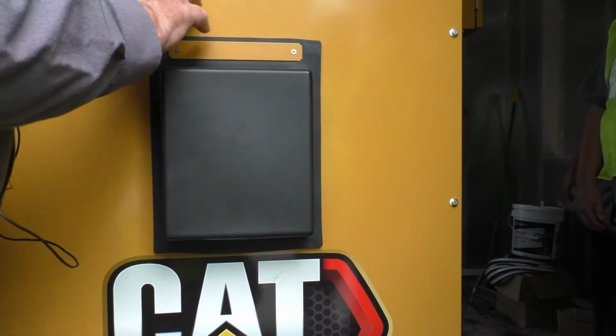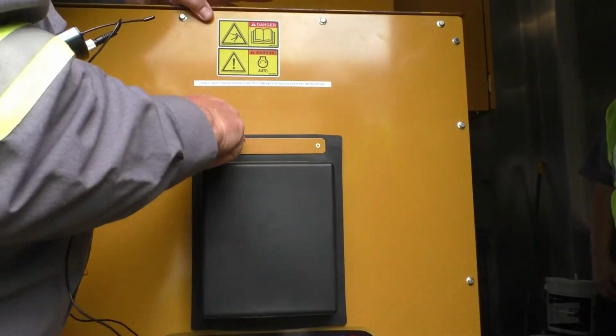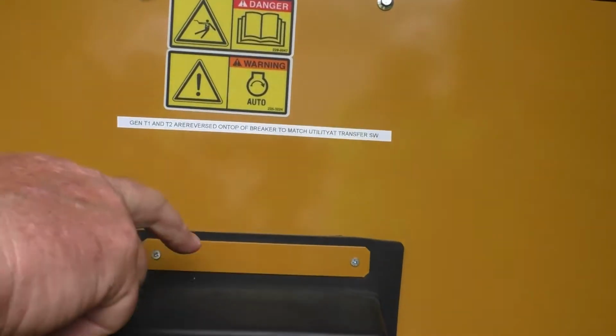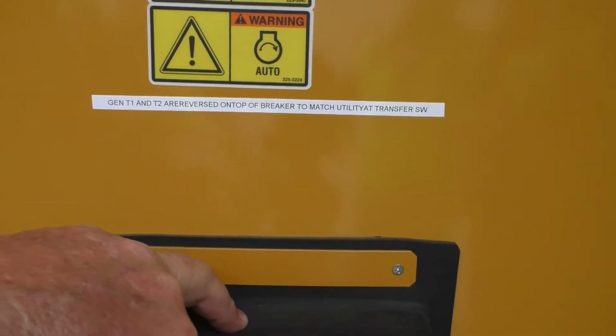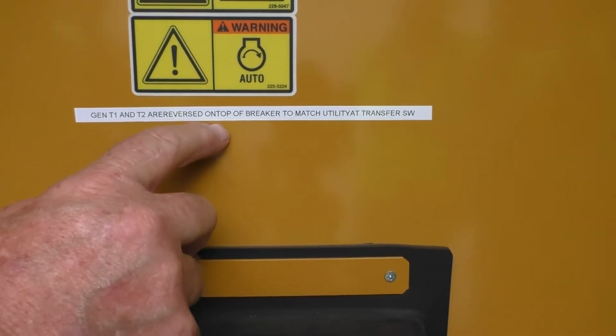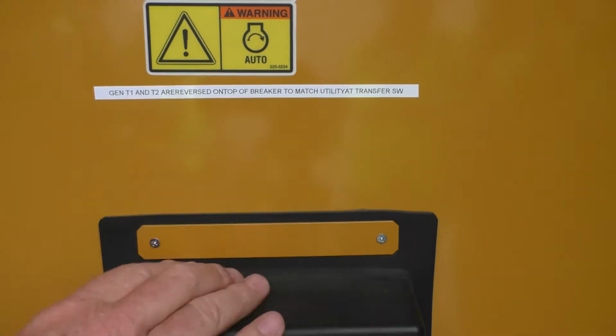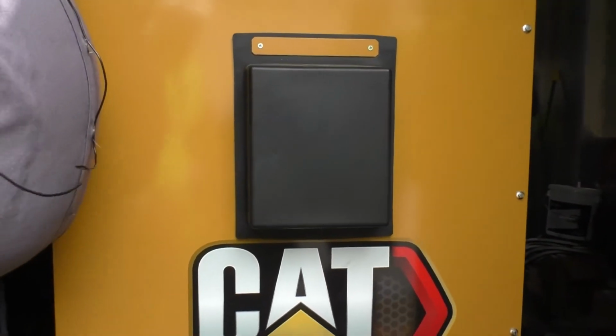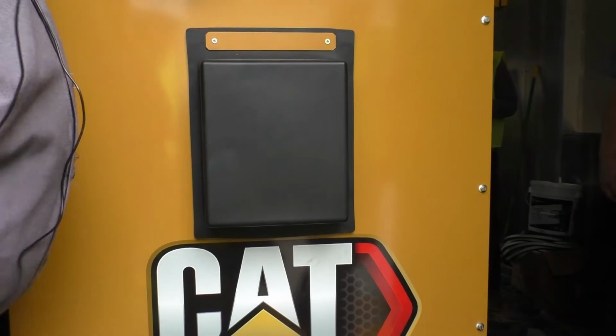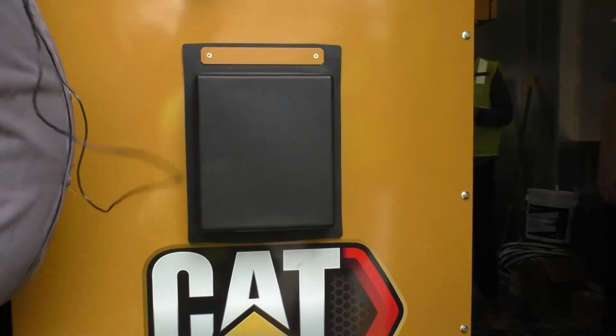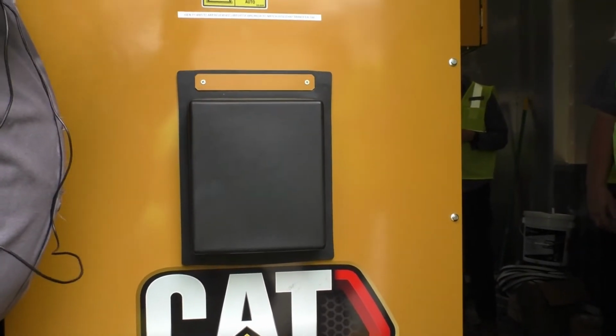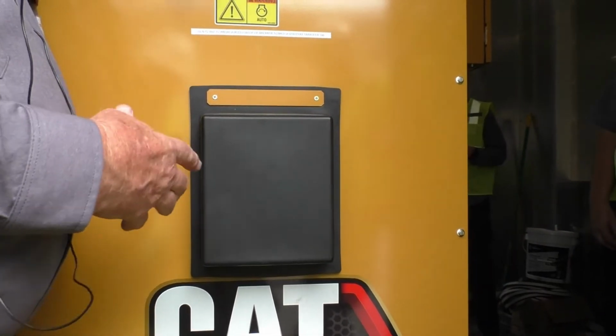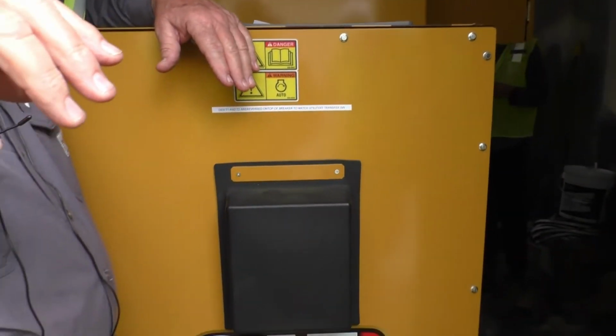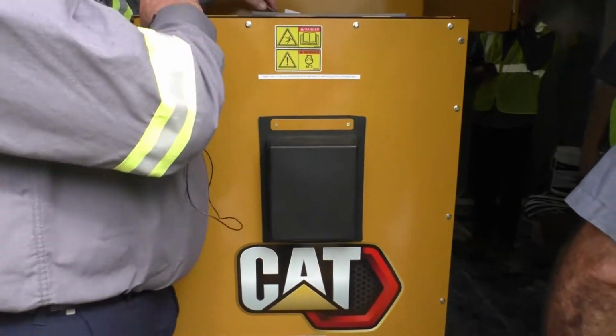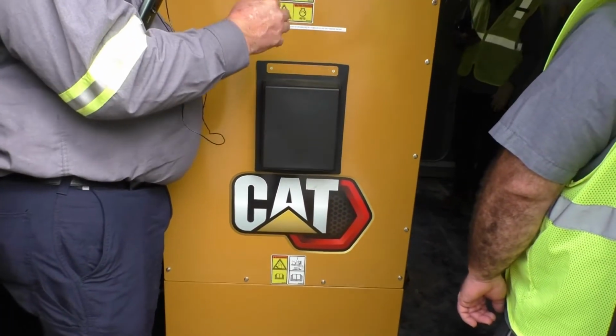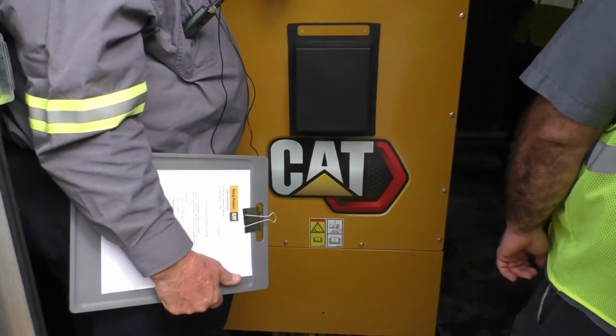The other thing, I know this probably doesn't matter to you guys, but I put a sticker here because we had to change phase rotation to match the building, and we changed it on the top of this breaker. I made a sticker: T1 and T2 are reversed on top of breaker to match utility at transfer switches. So it's for whoever's working, electricians or whatever. We're clockwise rotation, utility here is counterclockwise. Flip two leads and you match. So that's what we did here. All the cabling still matches on the other end. We wanted everything to be brown, orange, yellow throughout, so it all matches. It's a logical place to fix it.